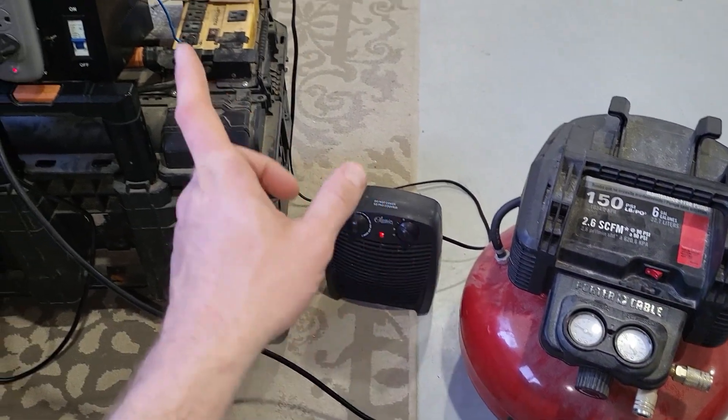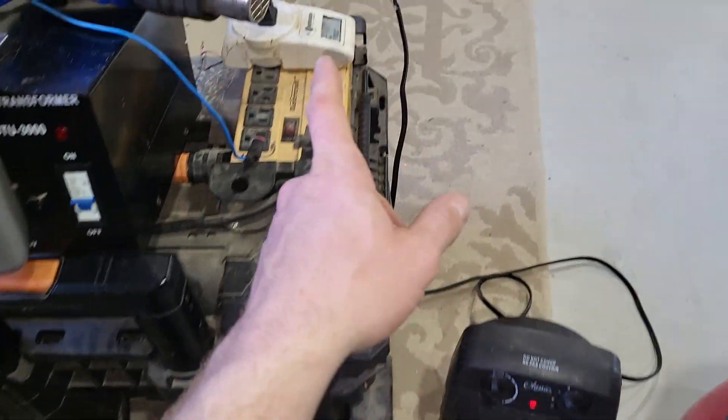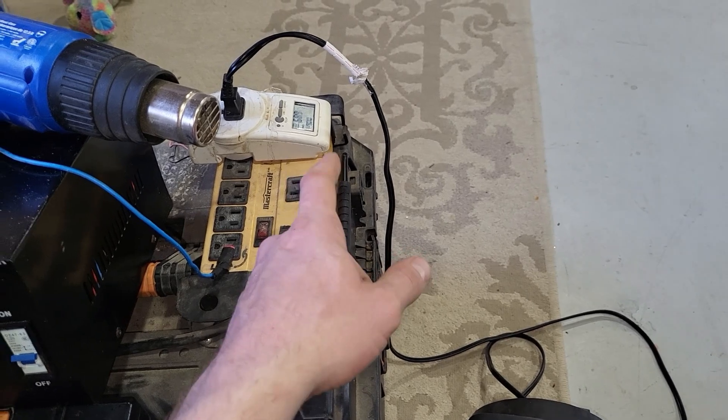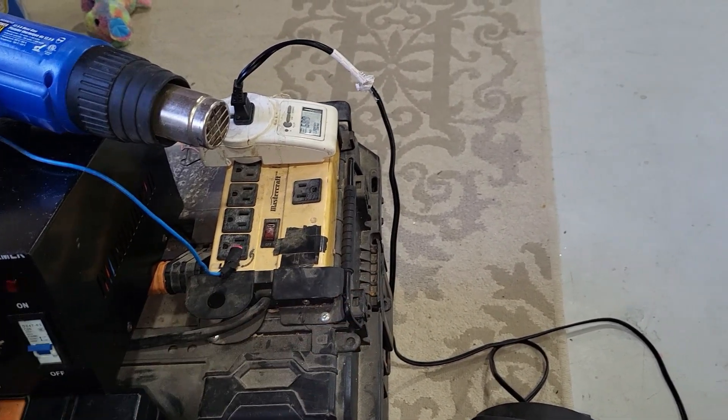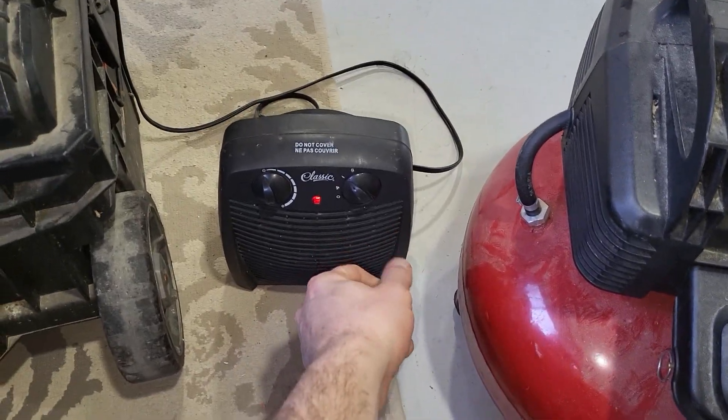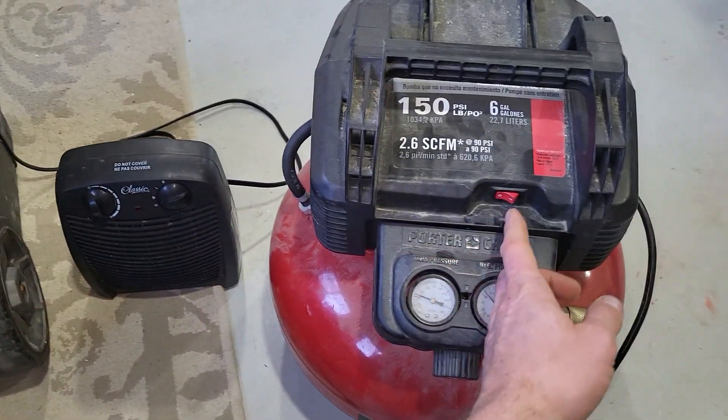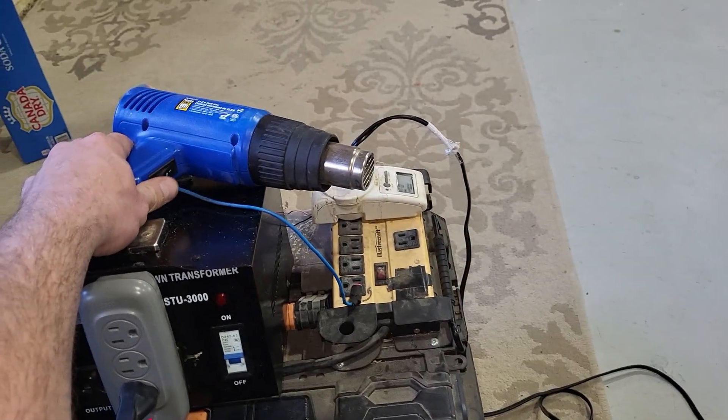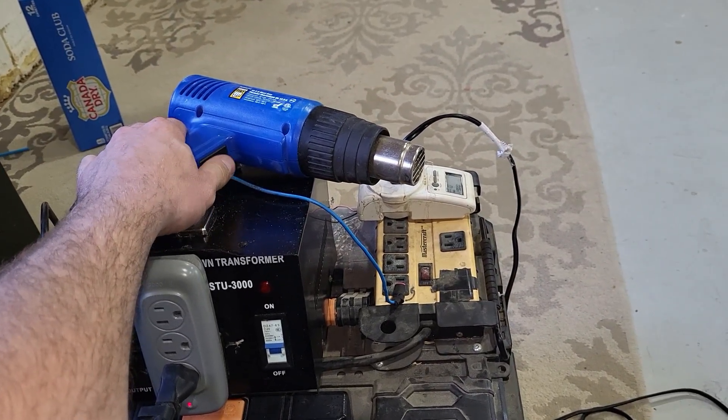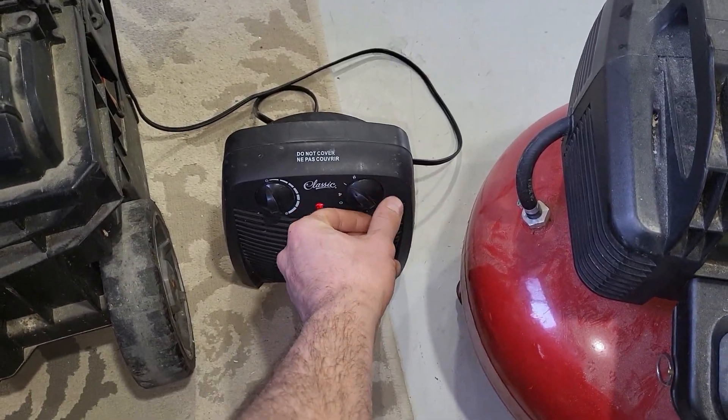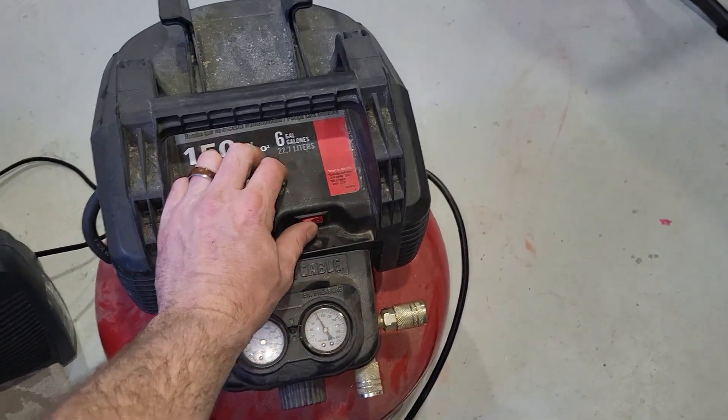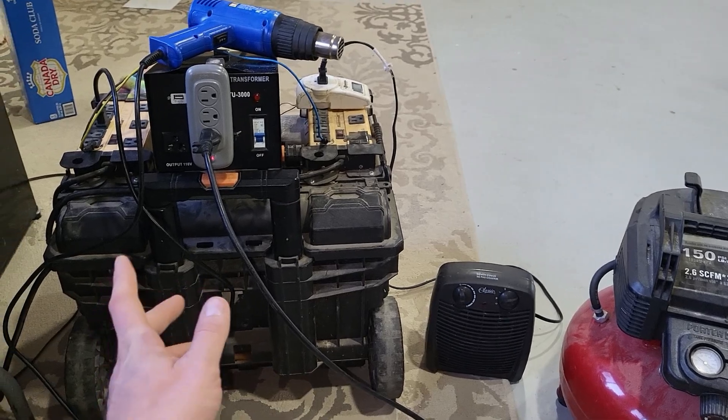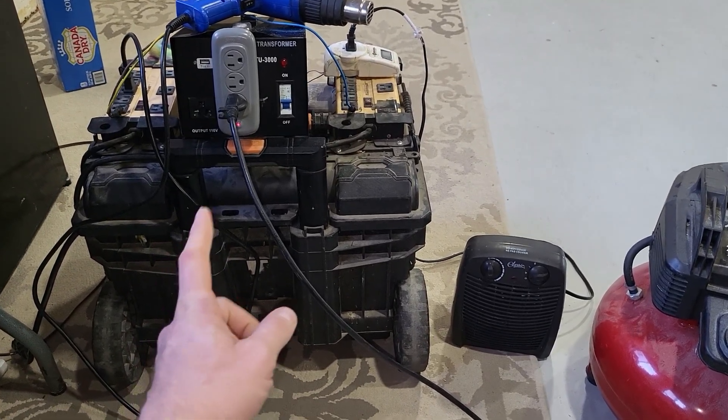Okay, it won't overload but obviously the voltage is drooping so bad I can't even show you on this meter because it goes to square wave and this meter reads like 150 volts. So let's try, oh boy, can't really just try one, we could try one, let's try one. That helped a little, turn this off. There you get the idea. So that is a cheap split phase inverter versus a much higher quality.